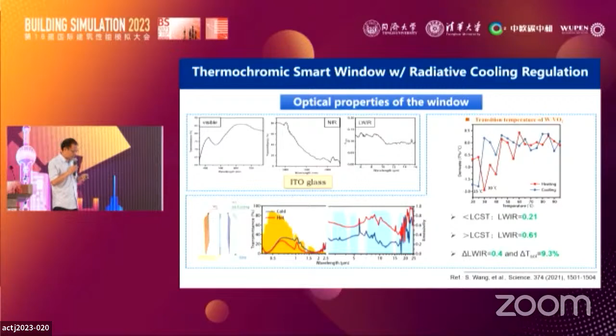For the simulation part, we conducted sensitivity analysis to see, for the exterior side of the windows, whether higher or lower emissivity would be preferred for energy savings. We found that for cooling, smaller solar transmittance and higher long wavelength infrared emissivity is best, but for the heating condition, it's reversed.